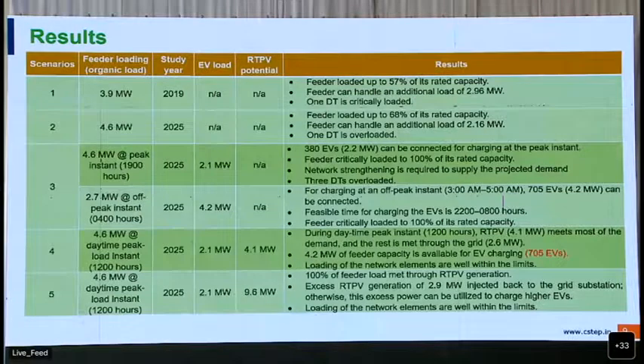In the first scenario itself, which is the existing case, we found that one DT is critically loaded. The existing load is around 3.9 megawatt. The first scenario is for 2019. The second scenario we did for 2025, where we considered a CAGR, the demand growth, of around 3.25%. With the same projections, the feeder is loaded up to 68% of its rated capacity, and the rest of the feeder is available for up to 2.16 megawatt. That means up to 2.16 megawatt of electric vehicle loads can be connected to that particular feeder.